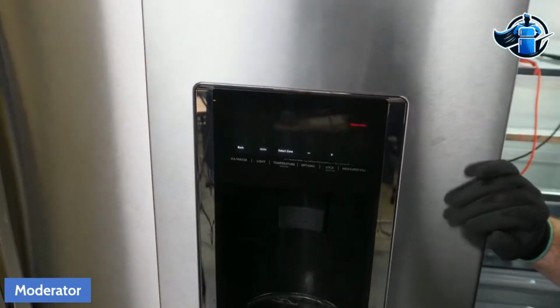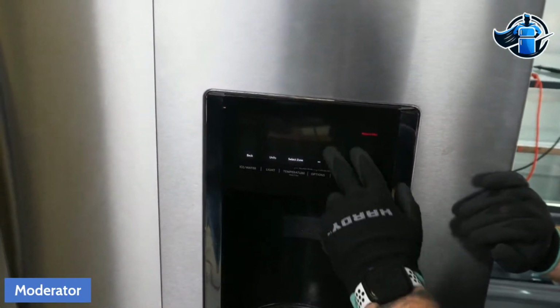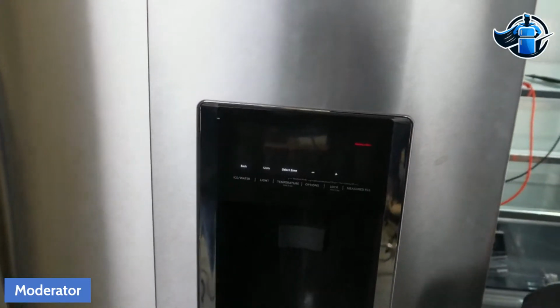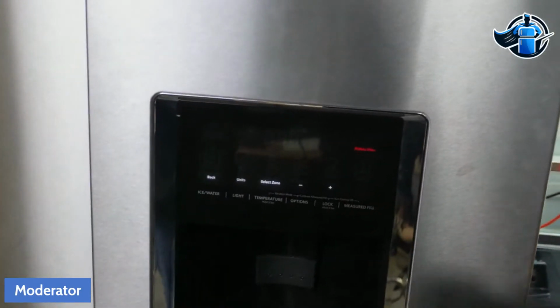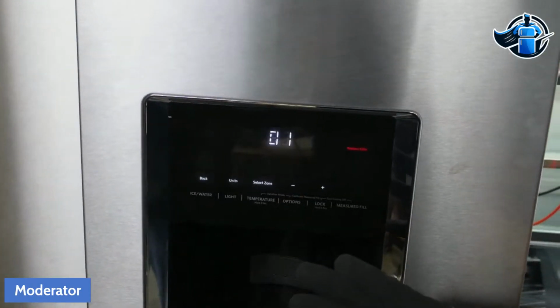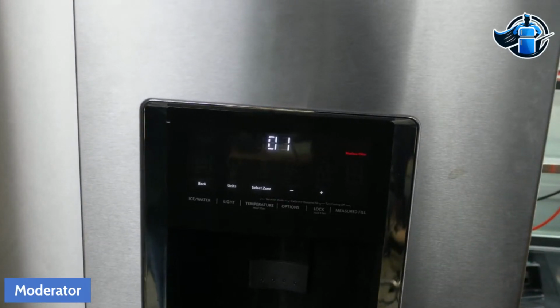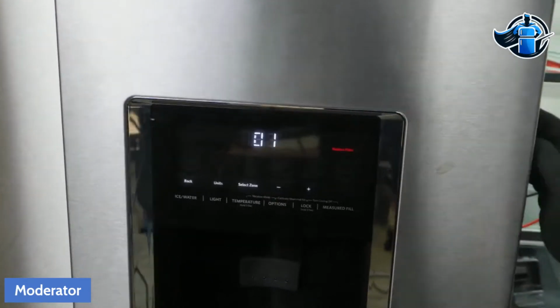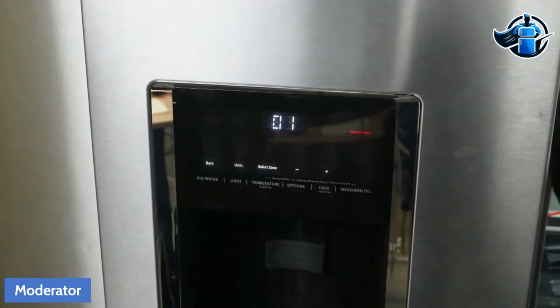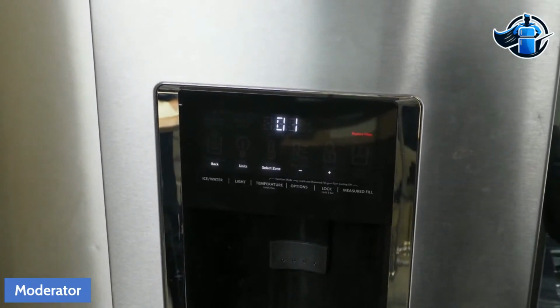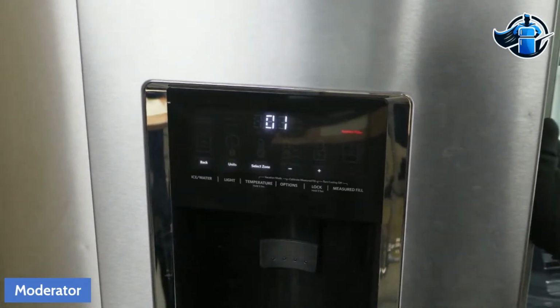You get an 02, that's a failure of the ice maker. So an 01 tells me the ice maker was able to do a full harvest. Again, that's about opening that switch when the ice maker starts, and then closing that switch on the return, telling the control board the ice maker made a full 360-degree turn, and it's back in home position.